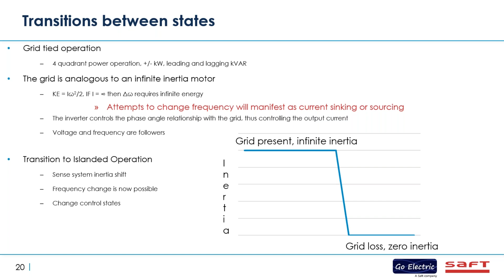So if we're going to transition to an islanded operation with a grid loss, you have the grid present with infinite inertia, you have a grid loss, and you can sense an inertia shift. So the frequency change is now possible where it was not before. You change control states and move into an islanded system. In an islanded system, the mode shifts from support to lead. So the inverter now controls the frequency and voltage. This operation is identical to fixed frequency motor control. So at a fixed speed, frequency and voltage stay the same and current is varied to meet required torque in motor control. It's another parallel between the two different systems.